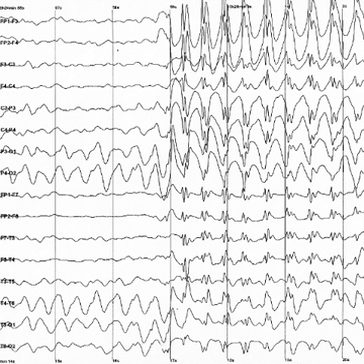Linked ears: a physical or mathematical average of electrodes attached to both earlobes or mastoids. Average reference montage: The outputs of all of the amplifiers are summed and averaged, and this averaged signal is used as the common reference for each channel. Laplacian montage: Each channel represents the difference between an electrode and a weighted average of the surrounding electrodes. When analog paper EEGs are used, the technologist switches between montages during the recording in order to highlight or better characterize certain features of the EEG.